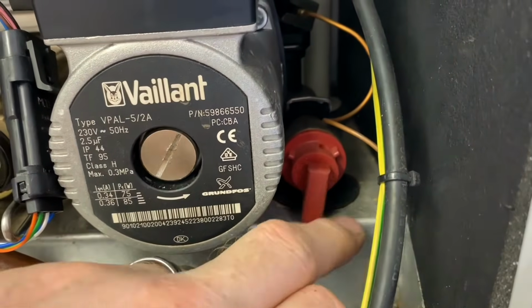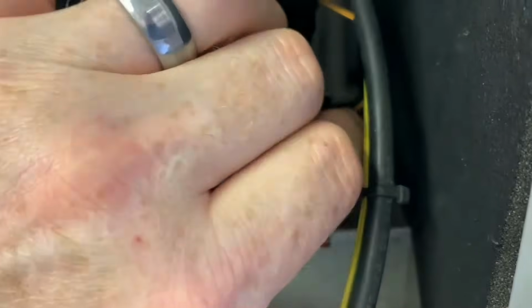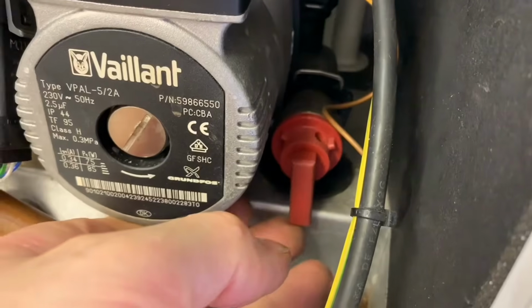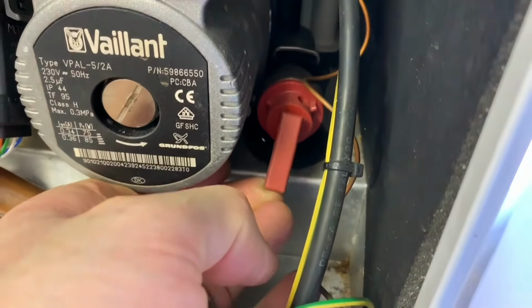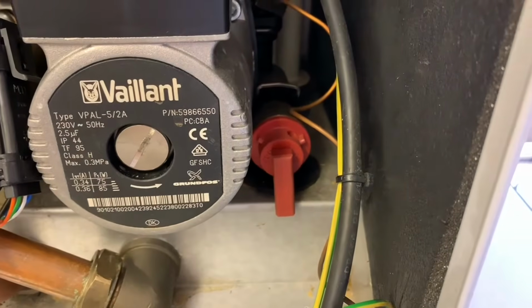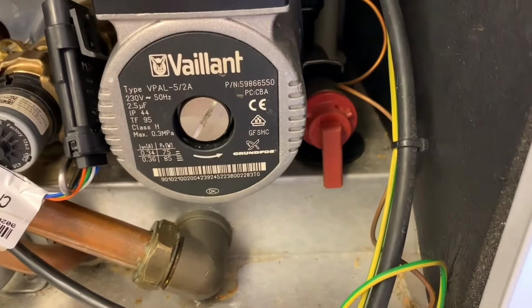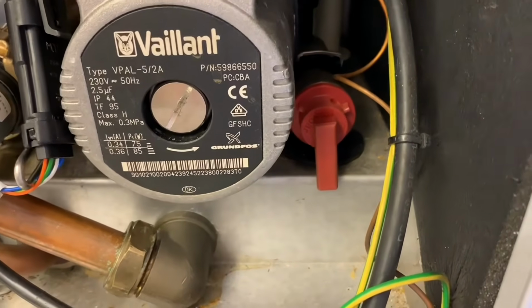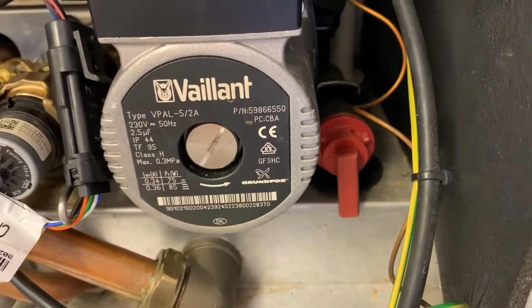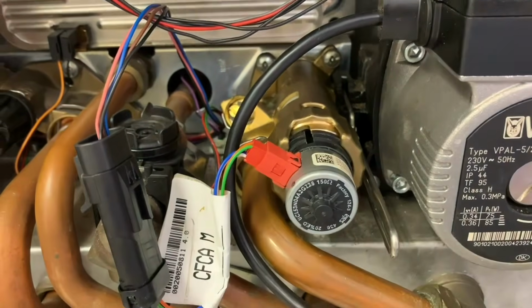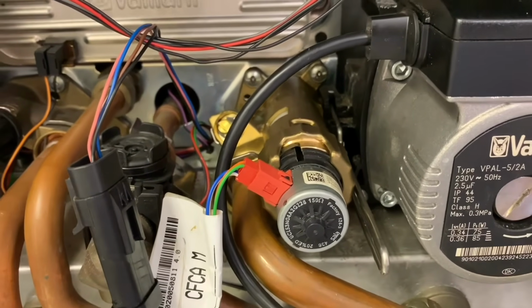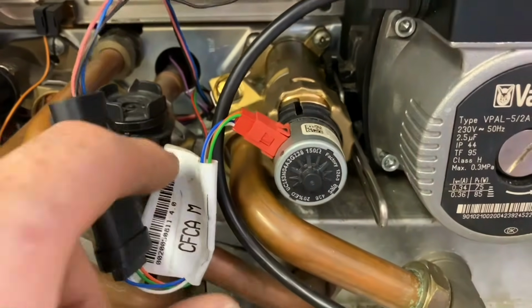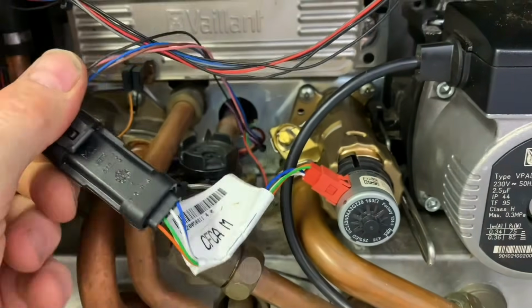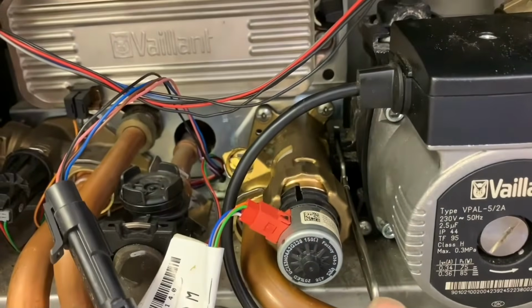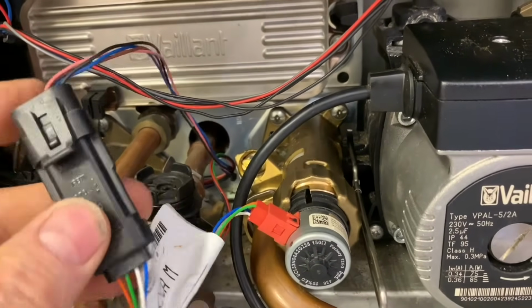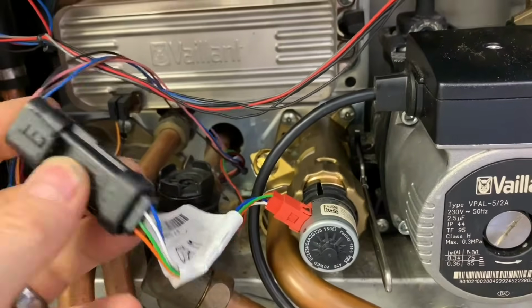Now, the thing you can see here is the 3-bar pressure relief valve with a handle to help us drain the system. If you pull that handle, it opens the actual pressure relief valve. Not a good idea really to drain a pressure relief valve because you get bucky systems and it damages them. So most boilers now put drains in rather than using the PRVs. If we come again to the left, this big shiny brass thing here is the diverter valve. Now this isn't the original diverter valve out of this boiler, this is a replacement one. And you can tell it's a replacement one by this electrical connection, what you get with it. So this is one of the new universal ones which will fit all the Pros and Pluses. So you get this universal connector.